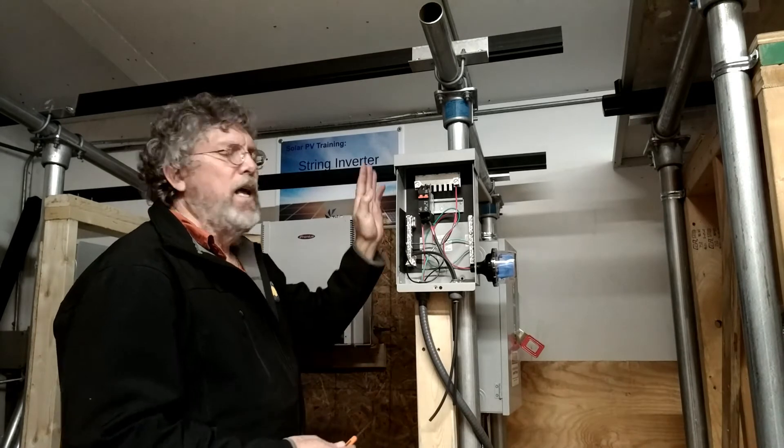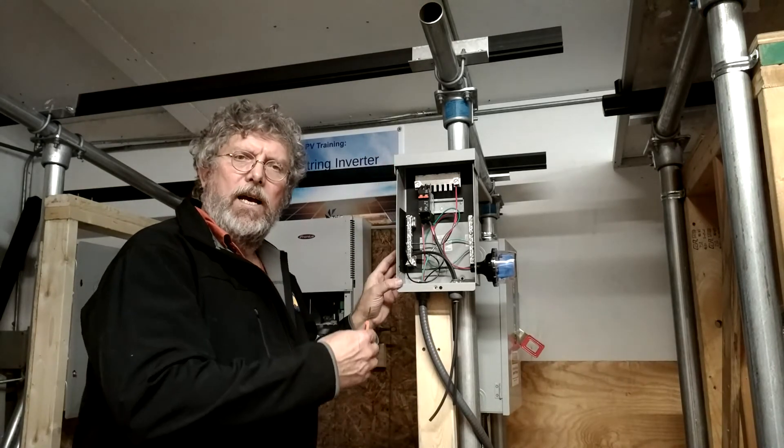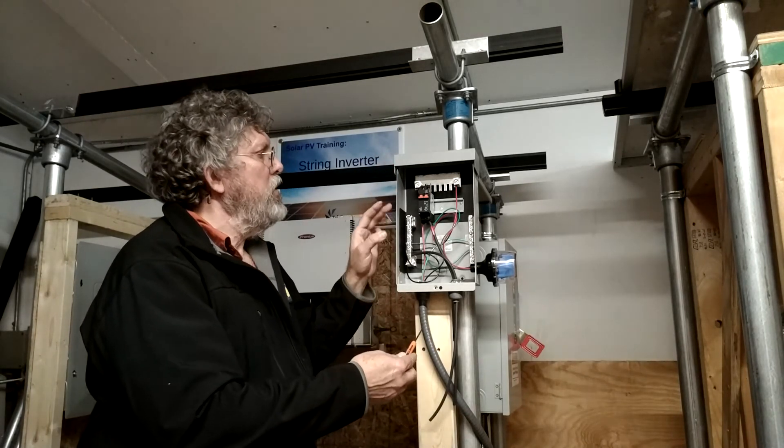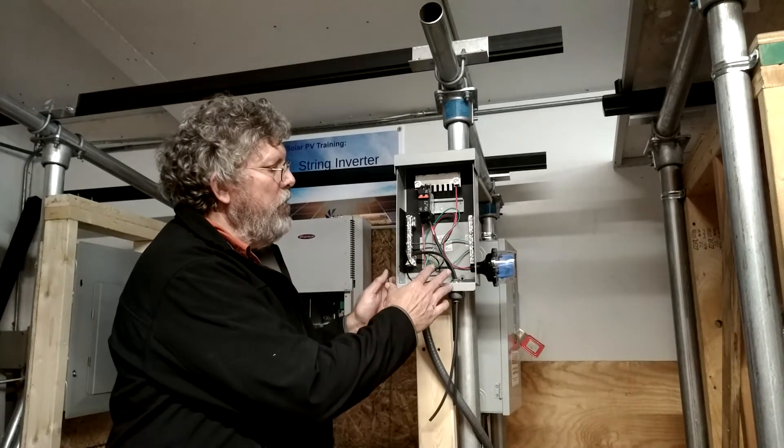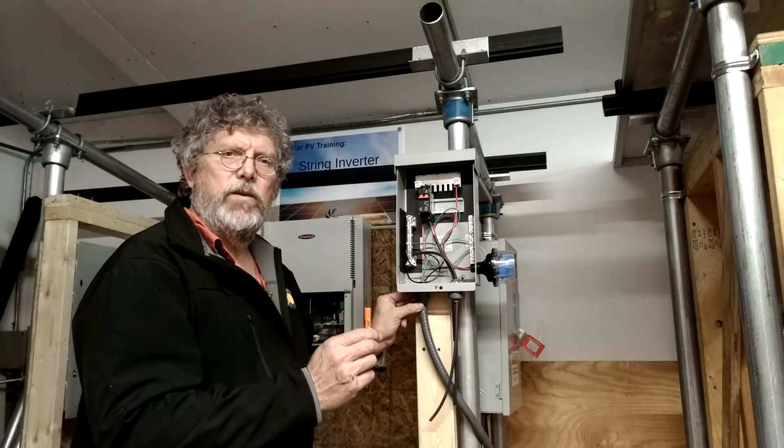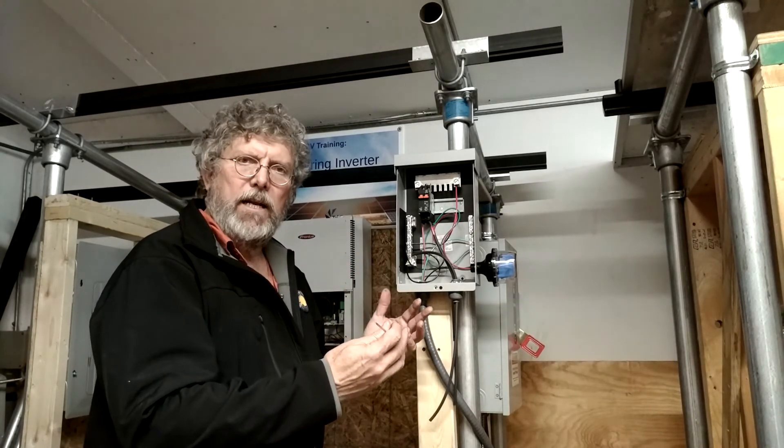Now the PV source circuit which comes from the array to the combiner box allows us in a traditional system to combine multiple strings and then lead from the combiner box to the DC disconnect with a single string. That just helps with wire management and the like.